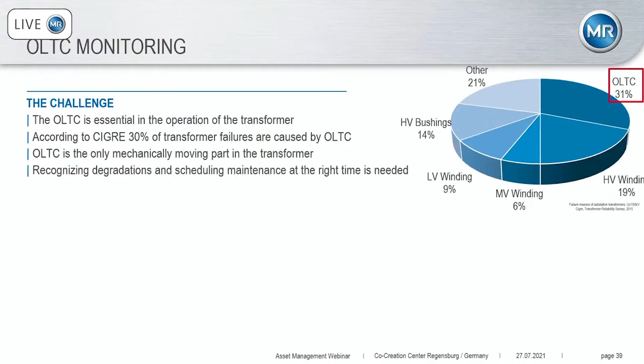Well, as we look at the Cigre statistics, among the reasons for transformer deviations and failures, we see the OLTC comes with 31%. Although the maintenance is conducted with all recommended measures, unforeseeable events can happen. The OLTC is the only mechanical part and the only moving part in the transformer, and for that reason, it is also subject to wear and tear. Well, there are solutions for that.